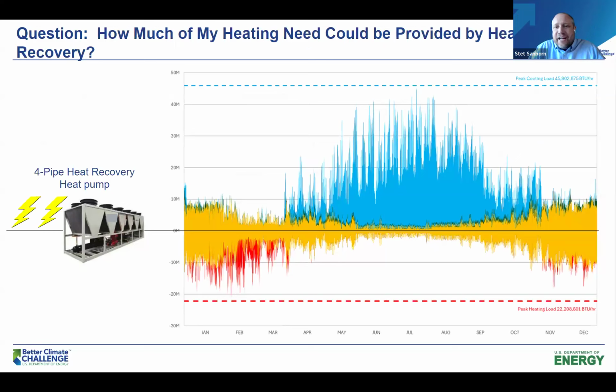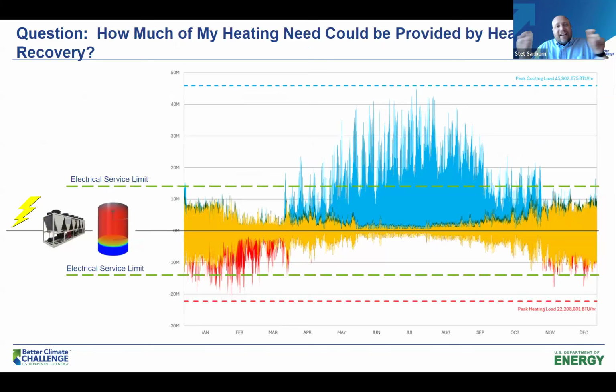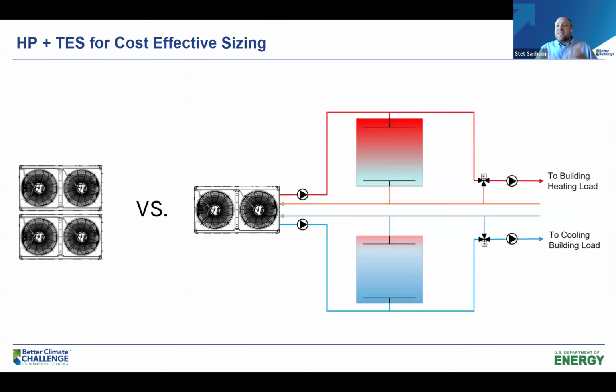But if that's not enough, if you say, well, Stet, I overlaid here my electrical capacity for the size of the heat pump, and this is the best I can do, I would come back and say, well, that's pretty darn good. We might be able to meet the rest of it with thermal storage. So instead of designing a heat pump that's really big and only operating for a few hours, let's right size a heat pump, pair it with thermal storage, and help pick up the gap. So this is what that might look like on an annual profile.